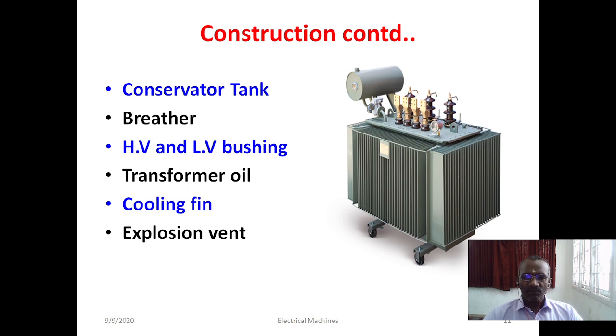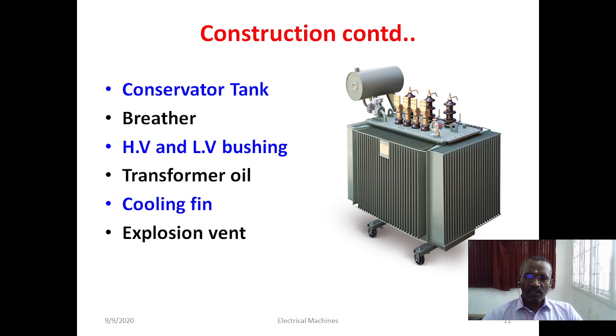We have HV and LV bushings. The main purpose of these bushings is to give supply to the transformer through the HV bushings if it is the primary side, and to take out the output voltage from the LV bushings if it is the secondary side. The transformer oil has high dielectric strength and is used for cooling as well as insulation between the winding and the tank. The oil absorbs the heat and it can radiate through the cooling fins or cooling tubes. Cooling fins are external fin-like or tube-like structures on the outer periphery of the tank, through which oil is circulated and the heat absorbed by the oil is radiated outward.